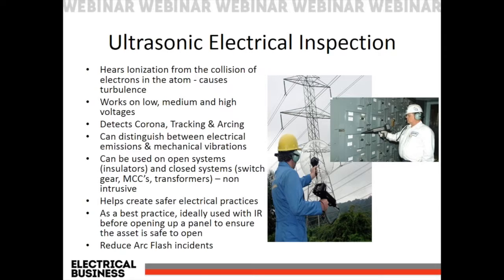You can see the picture of the gentleman here doing scans with our equipment, and we can literally look at those insulators on that tower and say, you know what, I'm hearing electrical emission there, and that emission is either corona or tracking or arcing. So we can diagnose that.